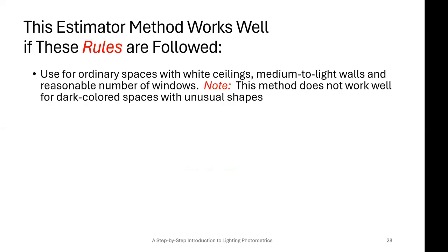So now, what are the concerns with this simple method? You've got some rules to follow. First of all, use it for ordinary spaces with white ceilings, medium to light walls, and a reasonable number of windows. If anything is extreme in your space, it's probably not going to work, especially dark colored walls, unusual shapes, that sort of thing. This is kind of like your typical room.